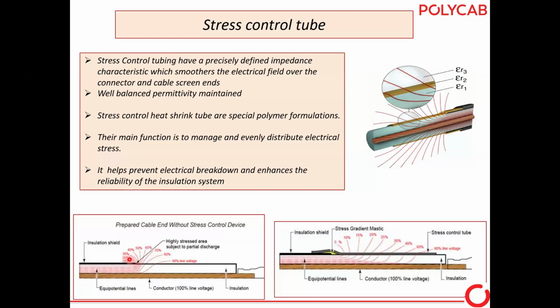So this is the earth part. This is the earth part. So the equipotential lines concentrate at this point. You can say 70-80% of the equipotential lines concentrate at this point, and failure will start at this point only. This is a highly stressed area and subject to partial discharge. If we do not use a stress control tube, or a proper stress control tube which has good impedance characteristics and well-balanced permittivity, then failure will start from this point only.